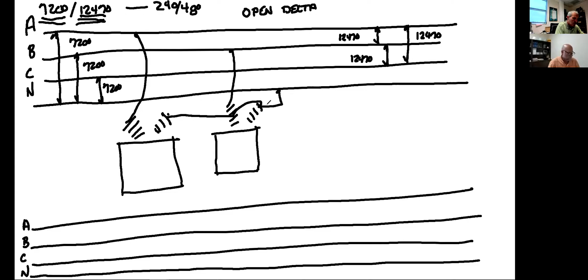What do I do with the neutral bushing, the grounded bushing on open delta? Do I float it or connect it to the neutral? Connect it to neutral. So I'm going to make a connection right here, both interconnected, and I took it to the neutral. In fact, my neutral's grounded. Now I've satisfied the primary connections on the top of the transformer.